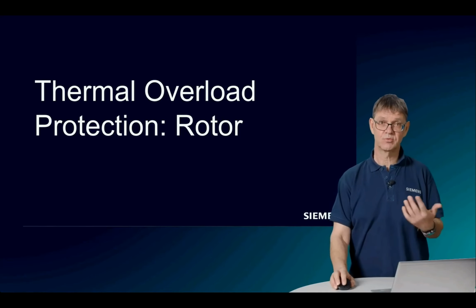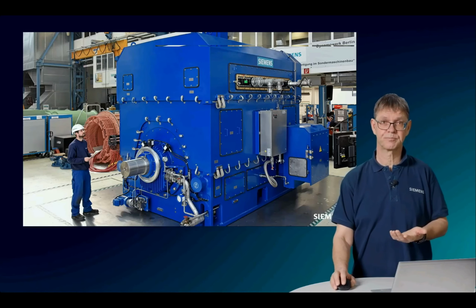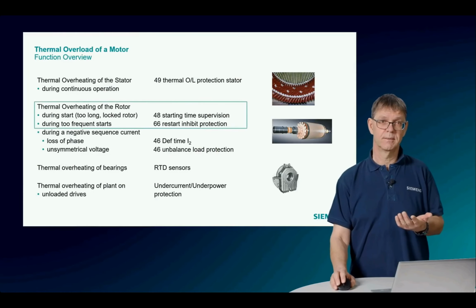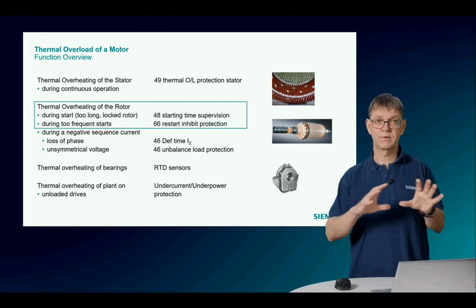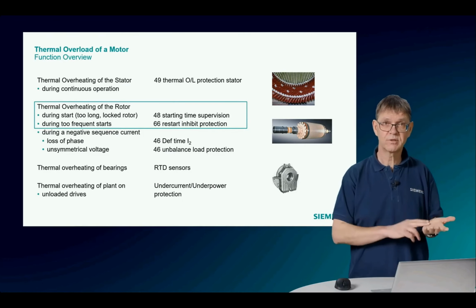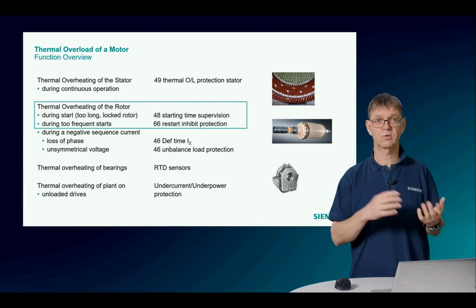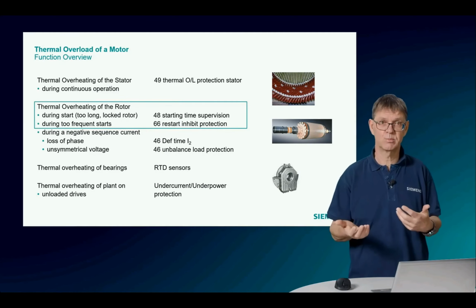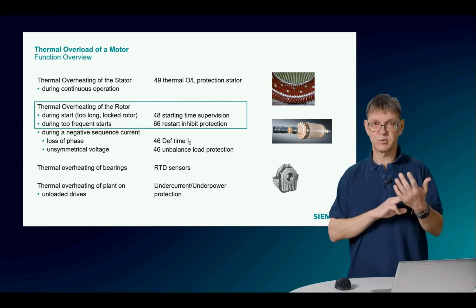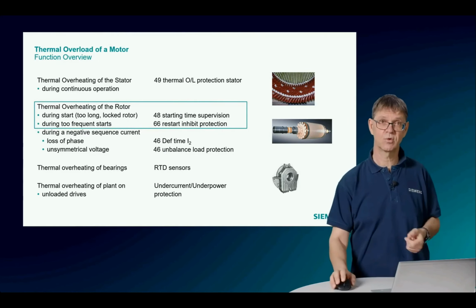Now let's come to the rotor overload protection. Here we first have a look at the two symmetrical problems. So with symmetrical currents, a too long start, a locked rotor situation maybe, or the protection against too many starts in a row.